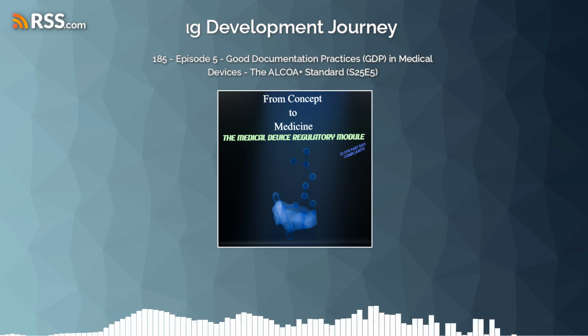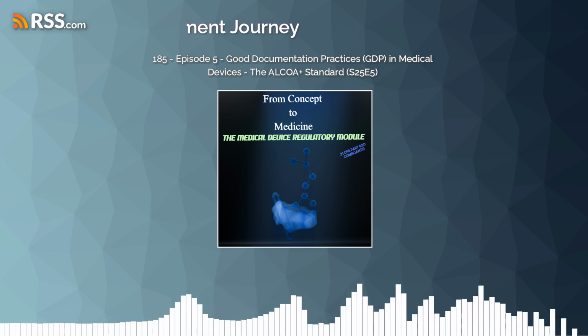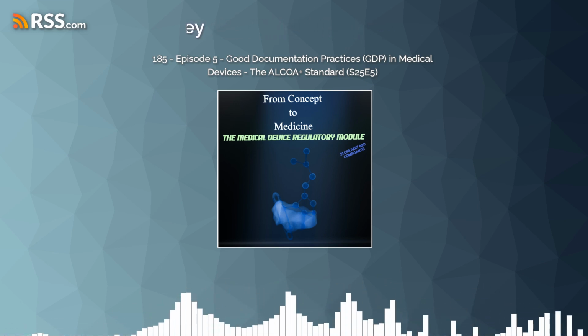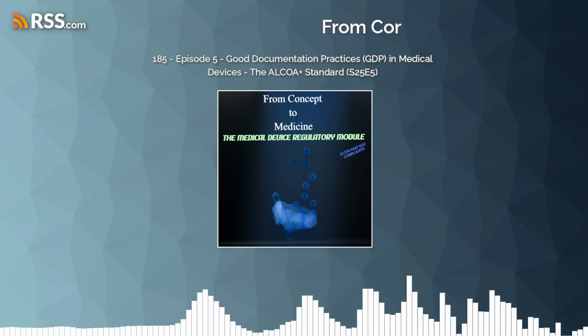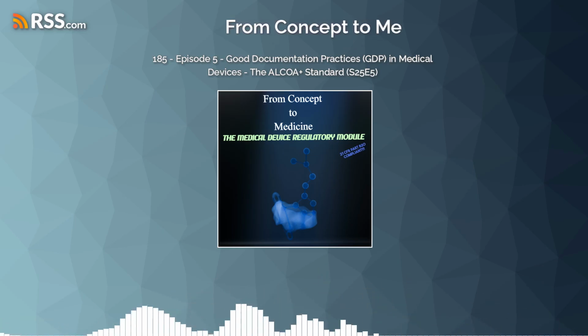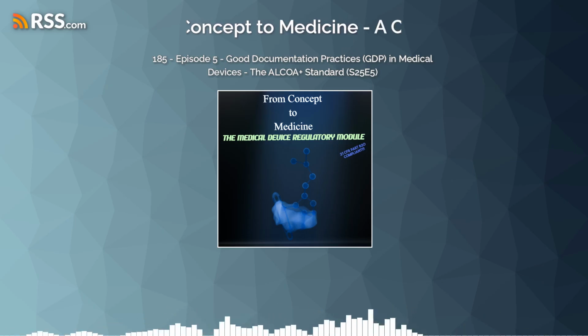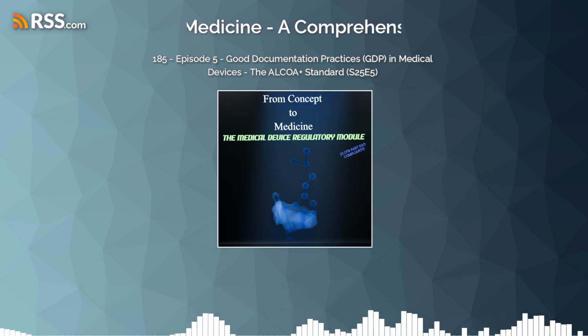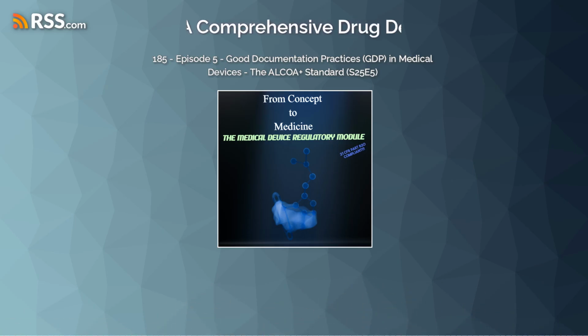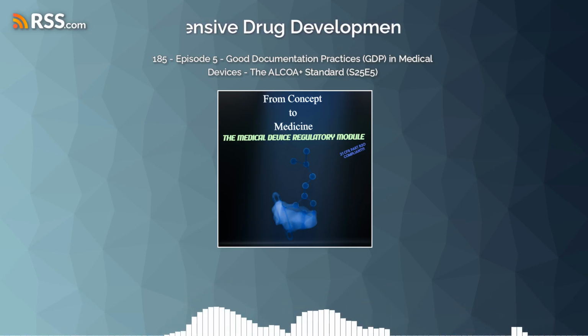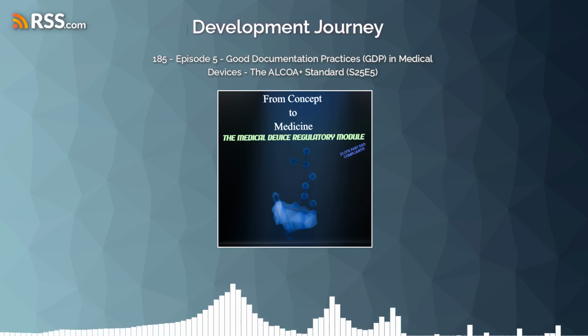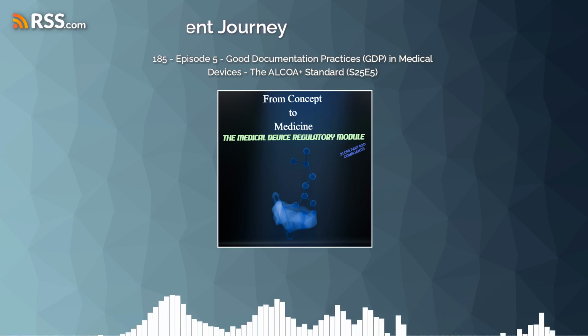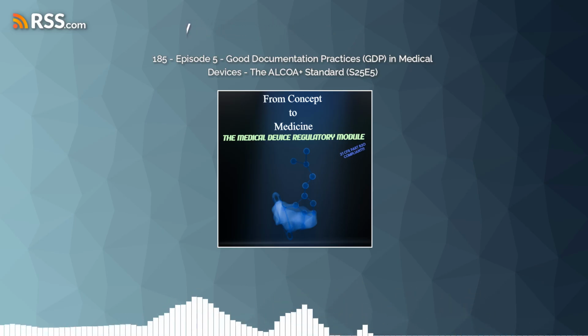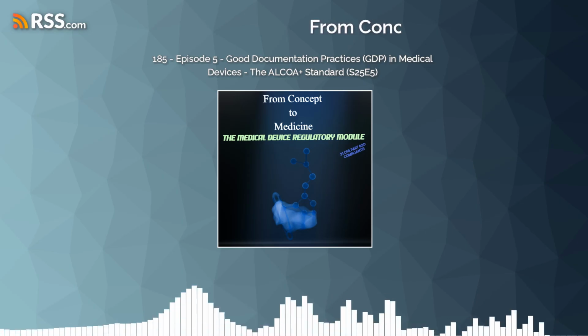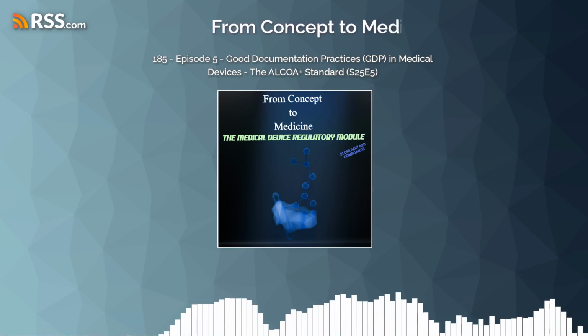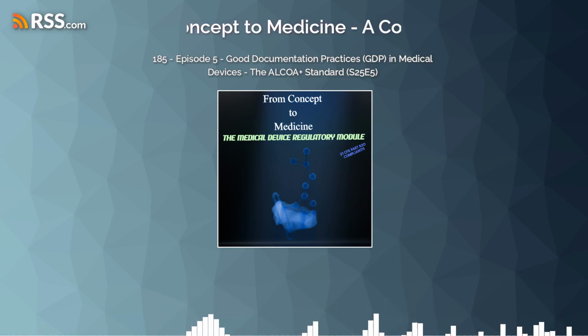That's a really important point, because things do sometimes go wrong. Maybe a component fails or there's an unexpected issue reported. Good documentation is your investigation toolkit. It's like that detective's case file we mentioned. Right. You can go back through the DHR for that specific batch, check the DMR instructions that were supposed to be followed, maybe even trace components back using lot numbers documented way back at the start. It lets you pinpoint potential causes, understand the root cause, and then take effective corrective and preventive actions, CAPA.